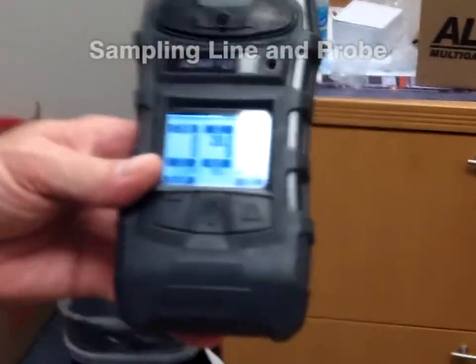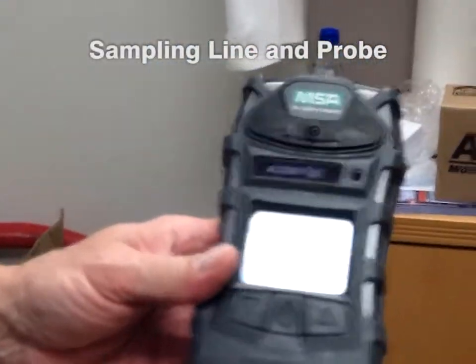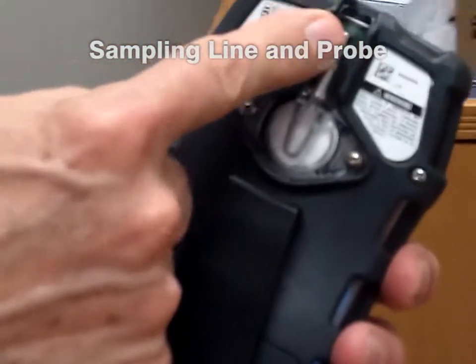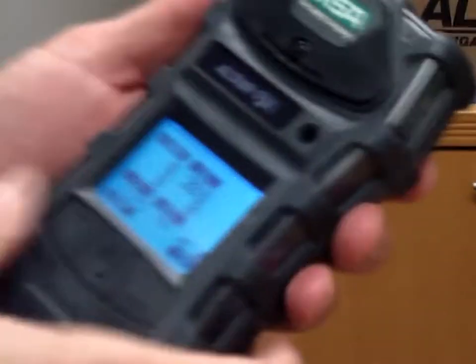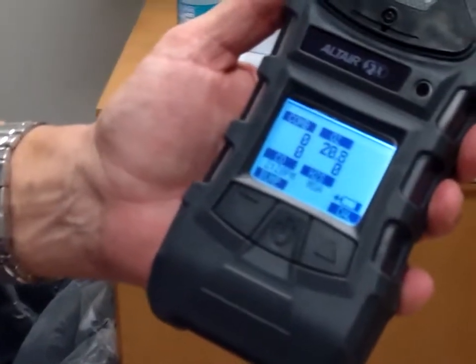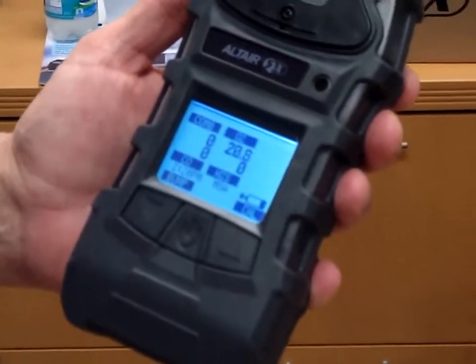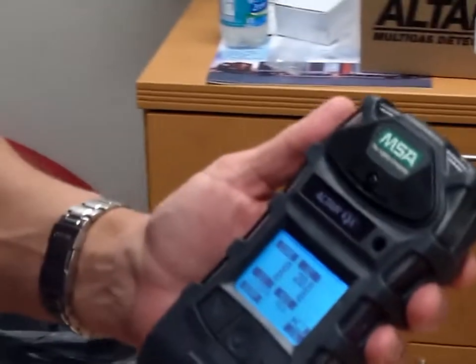Where do we go from here? We've got the unit on, up, and running. Now, proper use of the unit: right now, air from the area is being taken into this port right here, and that's being immediately delivered across the sensors so that you're going to get an immediate reaction. But you're going to be using this in a remote sampling type setup.